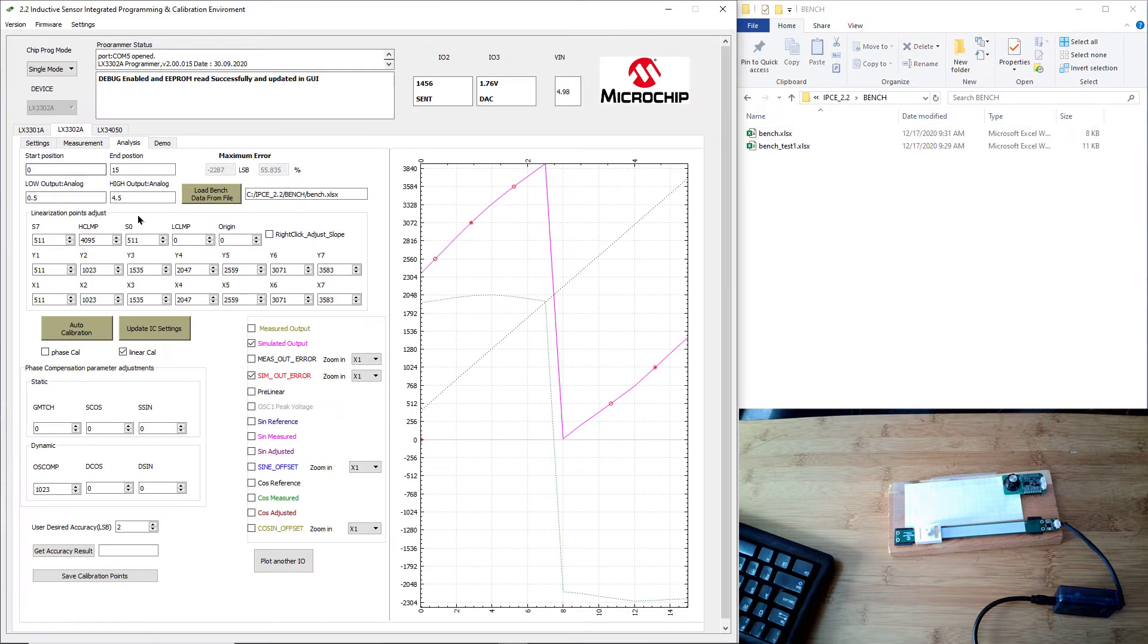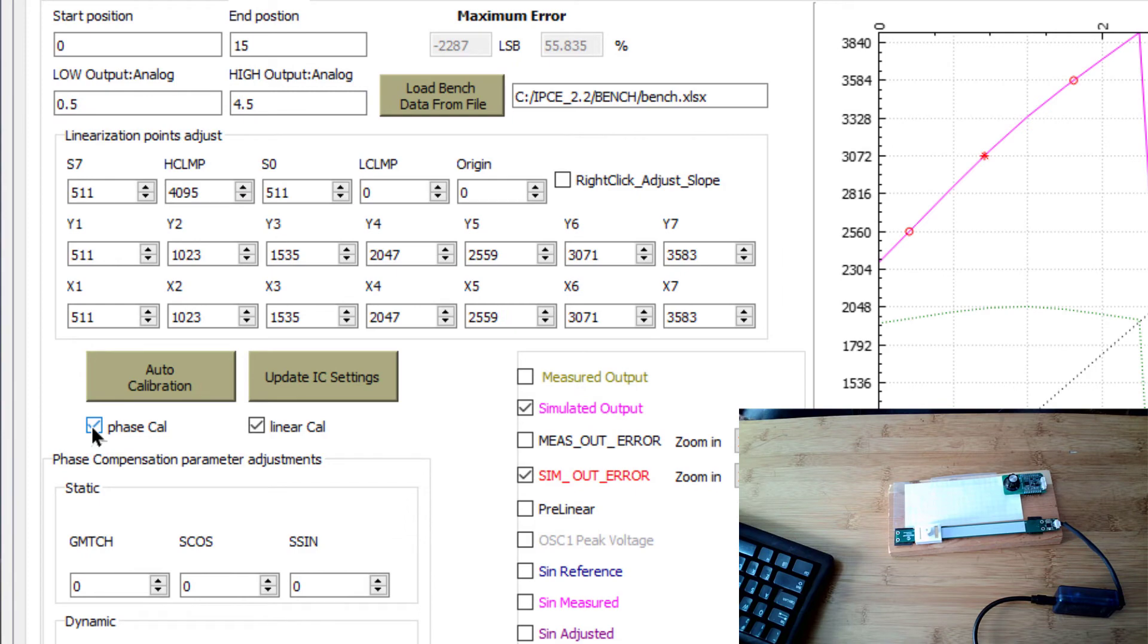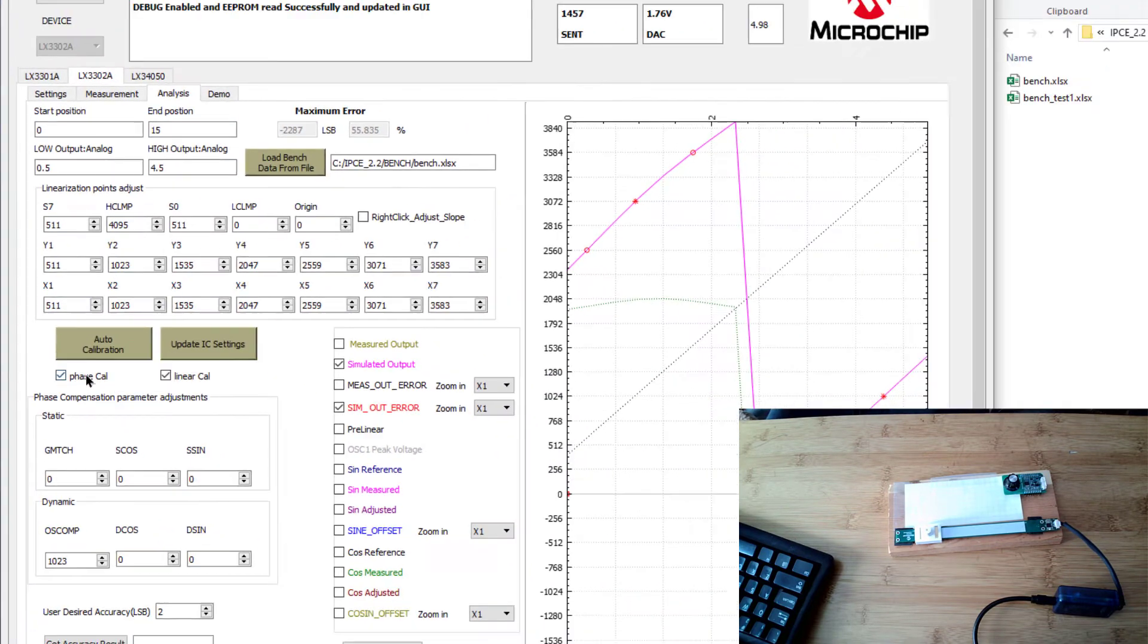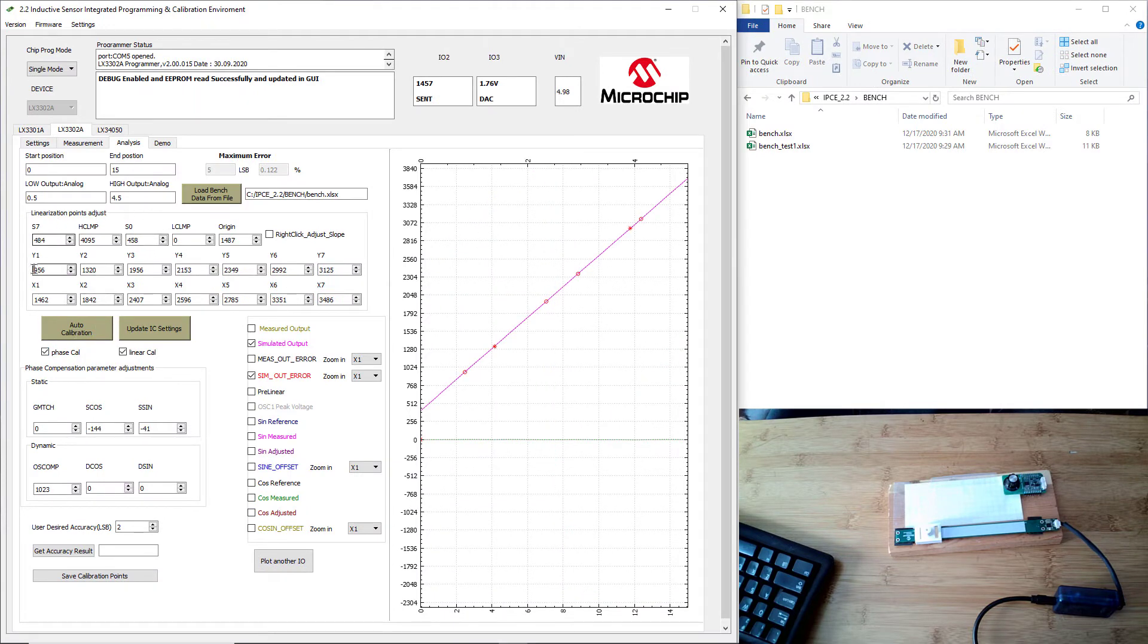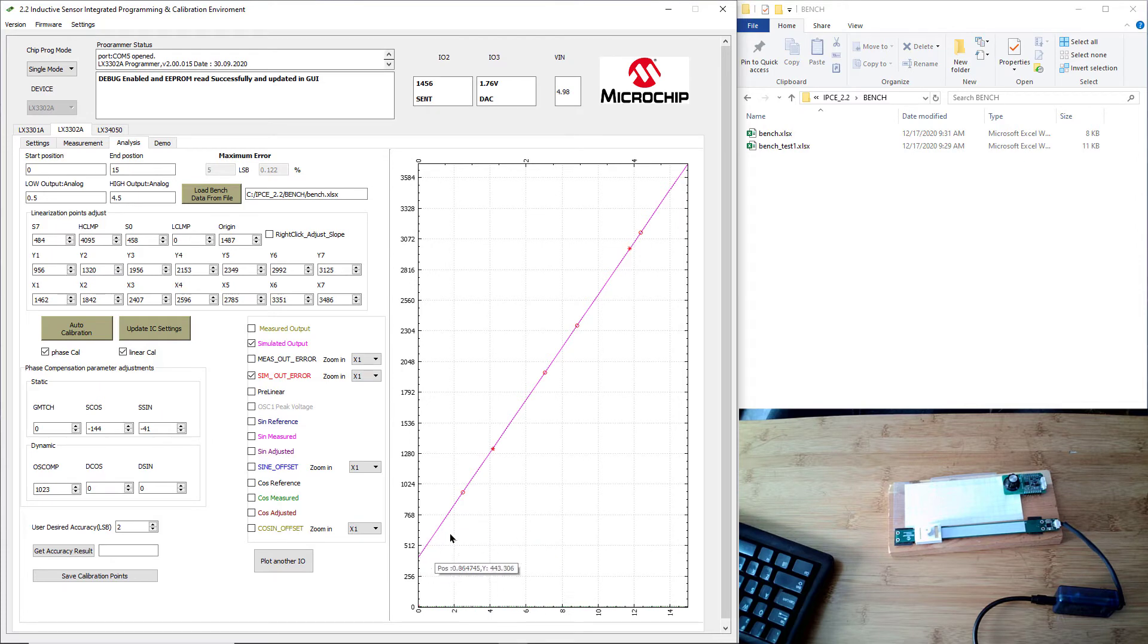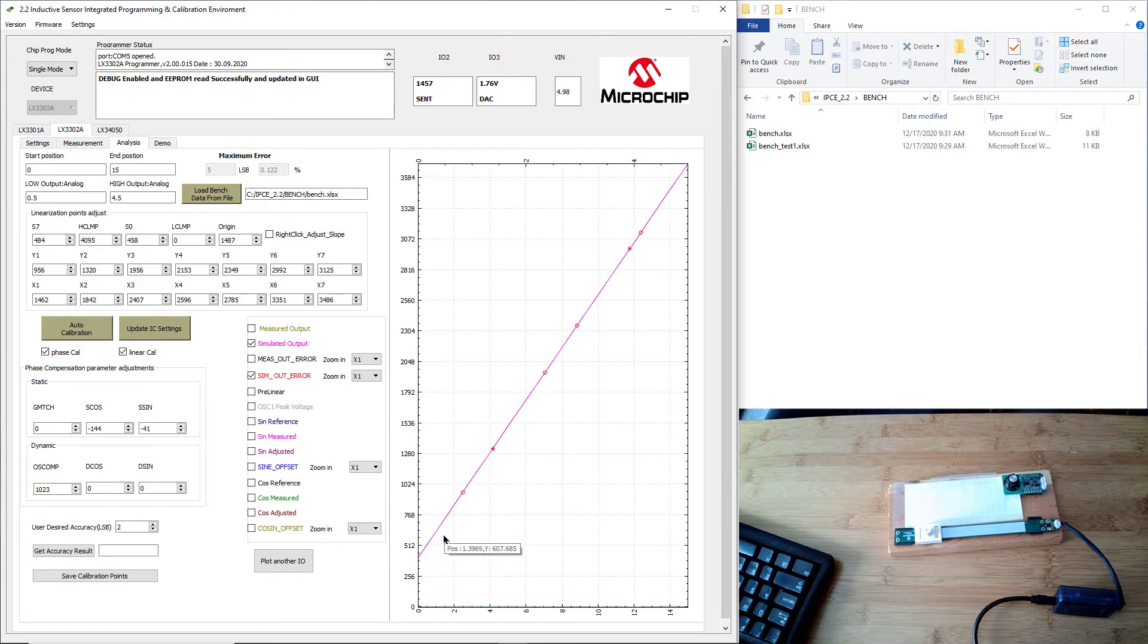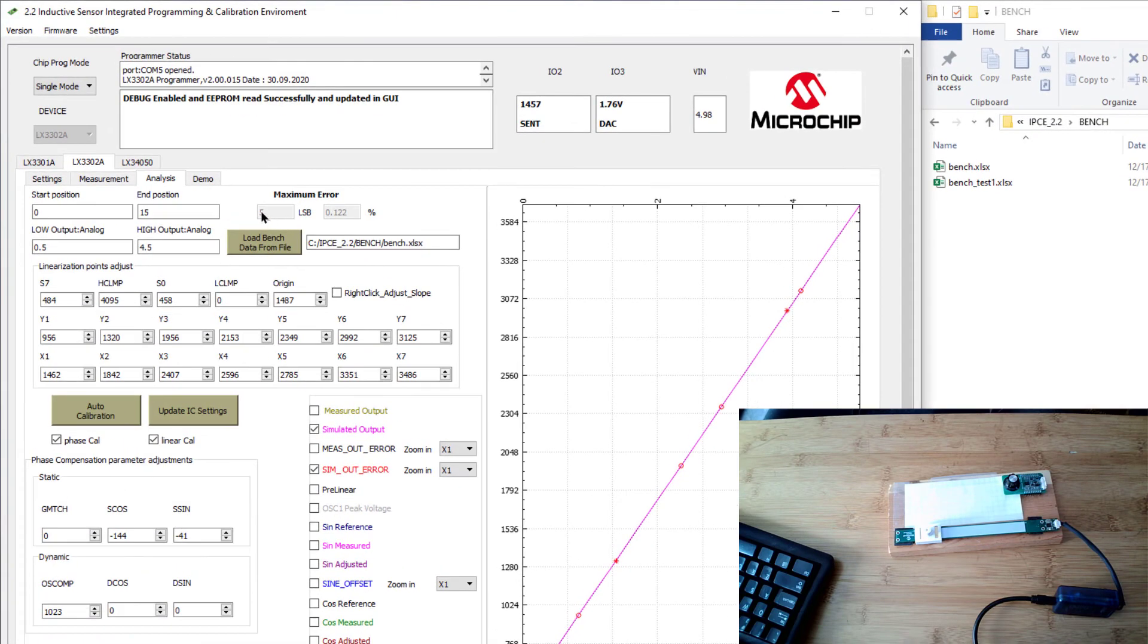In the analysis tab, you set those two, come down to here, and make sure you click phase calibration. Because we collected that debug information, we can hit the auto calibrate and get phase. Then we just hit auto calibration. What that's done is it will calculate the optimum values of these calibration points that are shown here to ensure that we have a straight line that matches an ideal line. It simulated the output and then calculates what it would expect the error to be if we had collected those data with these calibration points. It turns out it's 5 LSB or 0.122%.